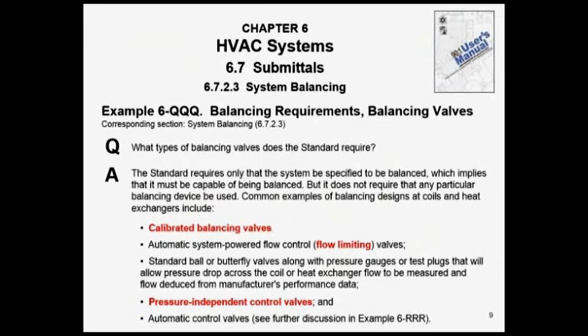And the first one you see is a calibrated balancing valve, which is the old concept. If I know the pressure drop across the device, I can take the Cv of that and come up with a GPM. Old-fashioned balancing valve that we've had for years. Next item was a flow limiter. Some people call these automatic balancing devices. They really are not. They are just plain old-fashioned flow limiters: if I specify a specific GPM and order this device at that GPM, it will not let the flow go over that flow limit. Anything below that, it is doing nothing. So basically the flow limiter is set for a max flow rate in GPM, which is fine.